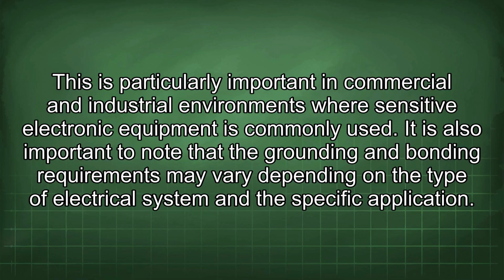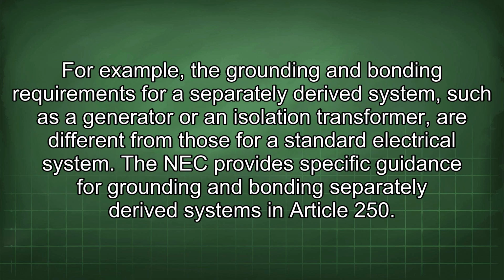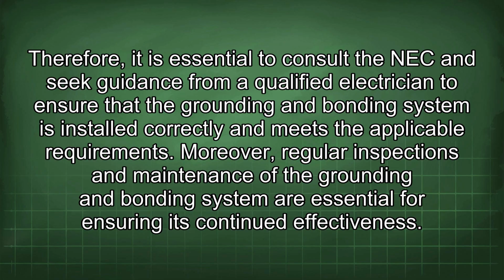It is also important to note that the grounding and bonding requirements may vary depending on the type of electrical system and the specific application. For example, the grounding and bonding requirements for a separately derived system, such as a generator or an isolation transformer, are different from those for a standard electrical system. The NEC provides specific guidance for grounding and bonding separately derived systems in Article 250. Therefore, it is essential to consult the NEC and seek guidance from a qualified electrician to ensure that the grounding and bonding system is installed correctly and meets the applicable requirements.